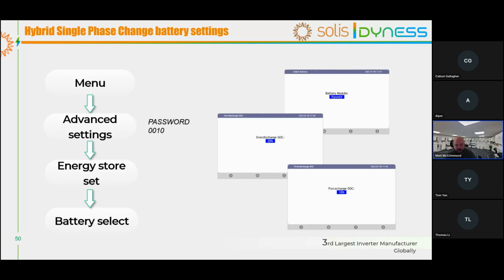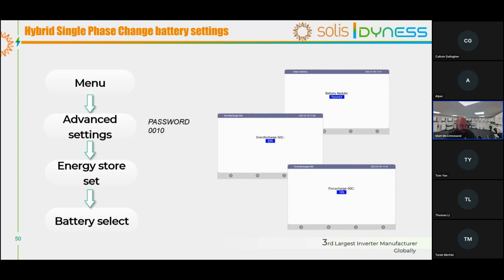We also have a forced charge SOC, which basically means that, for example, the customer goes on holiday, isolates the PV or the DC strings, but the battery is still keeping the inverter alive. So it has its own natural impedance plus also the load from the inverter to keep it alive. It will discharge further than 20% because it's not something that it can control. And then once it hits 10%, the inverter will then turn on the AC side to charge the battery back up. So you can set those values of how much power you pull back up until what percent. So ultimately, it's just like a safety net for your battery system to allow you to protect the investment.